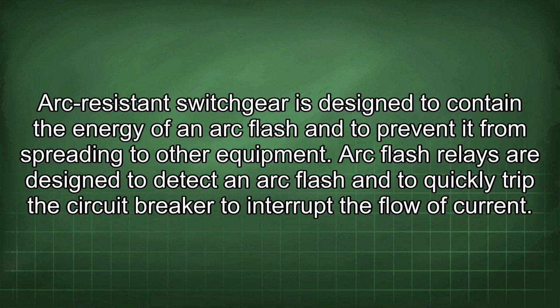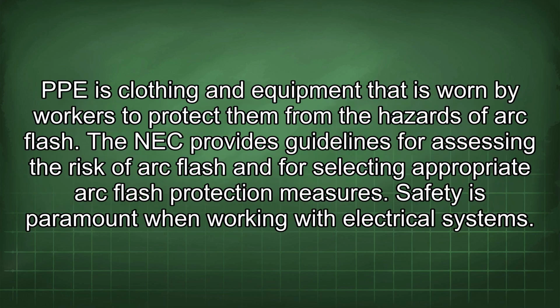Arc-resistant switchgear is designed to contain the energy of an arc flash and to prevent it from spreading to other equipment. Arc flash relays are designed to detect an arc flash and to quickly trip the circuit breaker to interrupt the flow of current. PPE is clothing and equipment that is worn by workers to protect them from the hazards of arc flash. The NEC provides guidelines for assessing the risk of arc flash and for selecting appropriate arc flash protection measures. Safety is paramount when working with electrical systems.